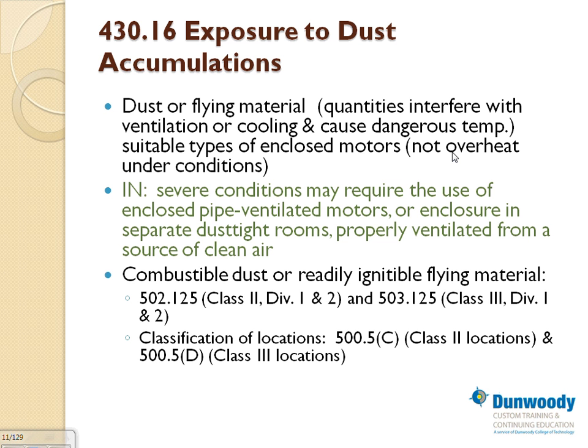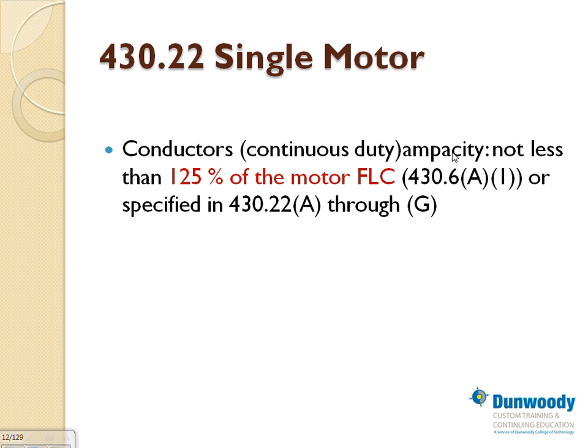So then you get into the combustible dust or readily ignitable flying materials. If you have a dust that can ignite, that moves you all the way into the class 2 and class 3 locations. Class 2 and class 3 locations. And we will touch on that one in a second. So a few things about that one. Single motors. We talked about this one, guys, when we size the motors. You take the full load amp, continuous duty, and you multiply by 1.25. So that's not a whole lot to it, and you size it based on that table.